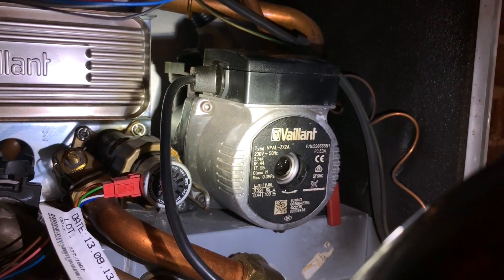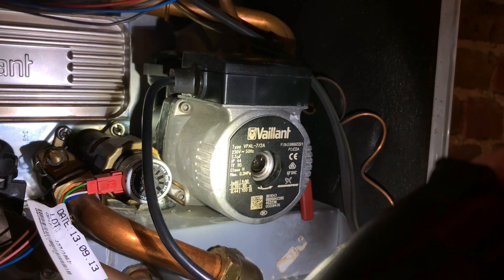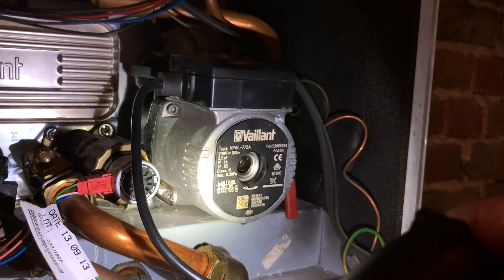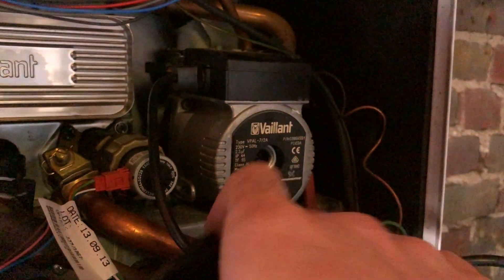In this case it's actually the pump that's gone and I'm going to replace it. It's normally between 160 and 200 pounds for a Vaillant pump like this and it's about an hour or so to change, so I'm going to go ahead and do that now. So if you've got an F75 fault it's normally just the low water pressure switch on the boiler, but sometimes you can get unlucky and it's a pump like this, or very occasionally it's a circuit board. I hope that helps — contact details are on this video. Cheers, see you later.